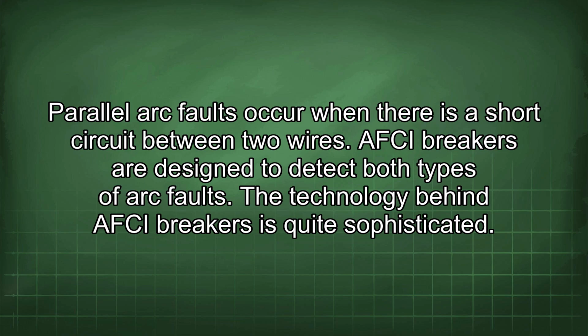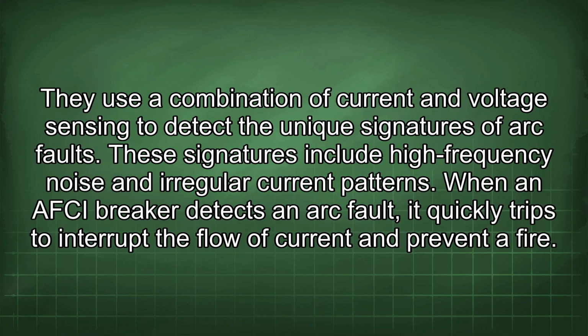Parallel arc faults occur when there is a short circuit between two wires. AFCI breakers are designed to detect both types of arc faults. The technology behind AFCI breakers is quite sophisticated. They use a combination of current and voltage sensing to detect the unique signatures of arc faults. These signatures include high-frequency noise and irregular current patterns. When an AFCI breaker detects an arc fault, it quickly trips to interrupt the flow of current and prevent a fire.